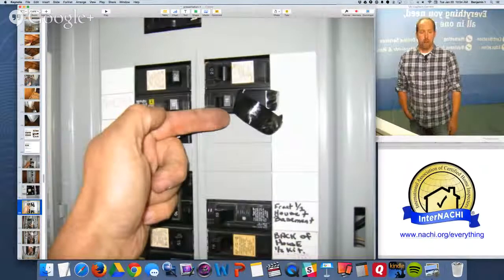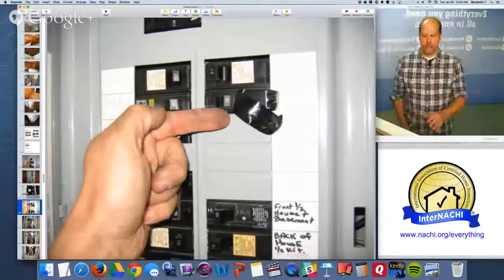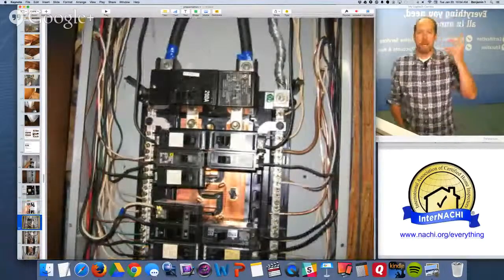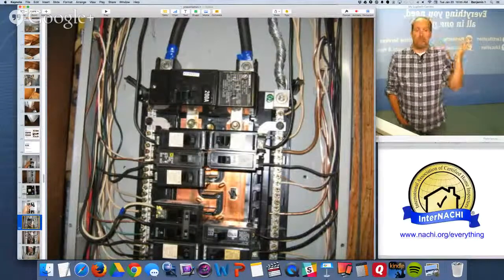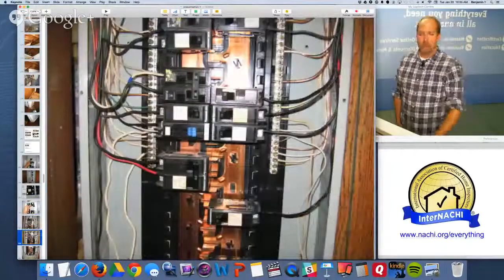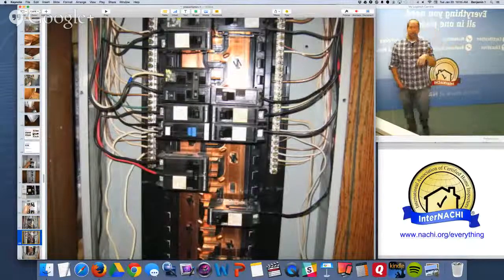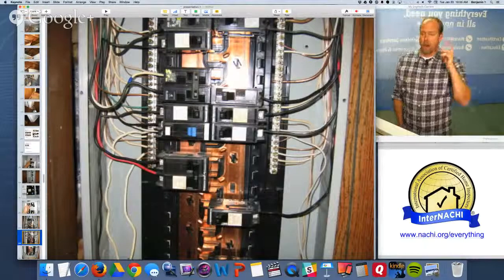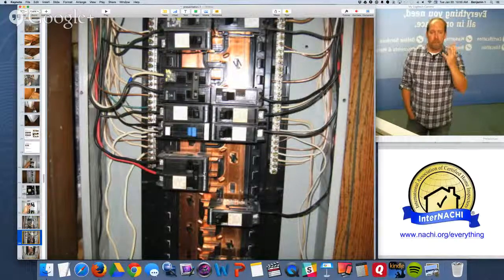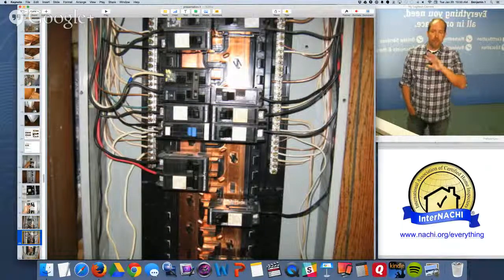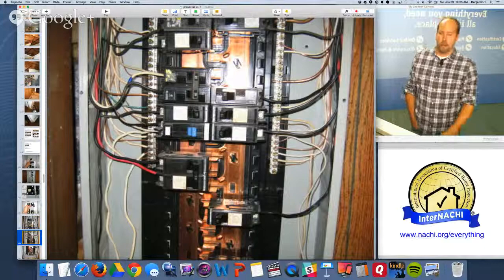Whether a breaker is tripped or turned off — don't turn it back on. Just identify it as a problem. Maybe that electric line hanging down is on that breaker — don't know, because it wasn't identified. You do not have to remove the dead front cover. If you do, wear PPE — protect yourself: gloves and goggles. Never open up an electrical panel and remove a dead front cover without PPE. Don't even take training from an instructor who doesn't use PPE during the inspection.